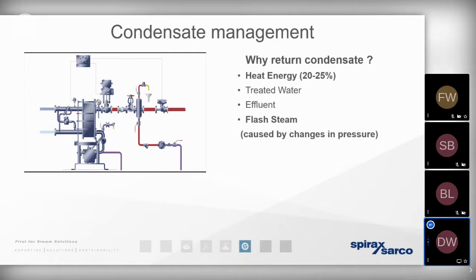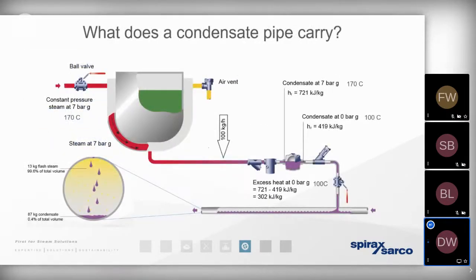But not only that, that condensate is still water. So the more condensate we can recover, the less raw water we need to consume. So condensate does have a value at the boiler house. It just doesn't have a value at the process.